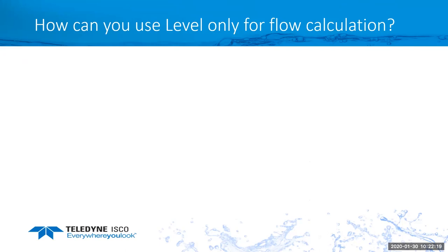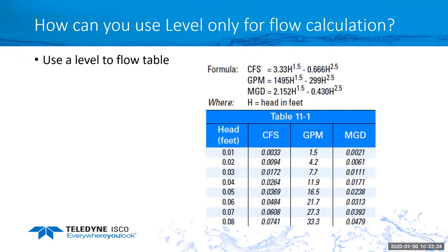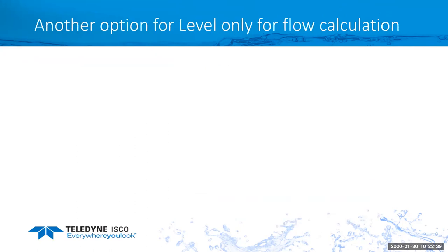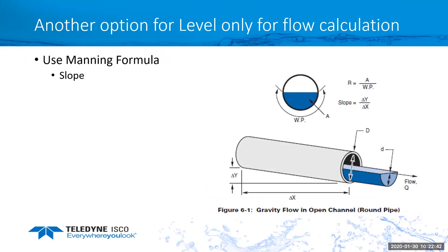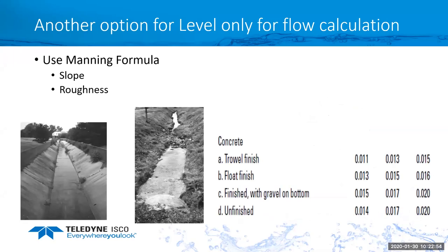So continuing on that, how can you use the level only to calculate flow? One, you can just use a level to flow rate table. The ISCO Flow Data Handbook has lots of tables in there depending on what your application is. Or you can use a flow calculation to determine your flow rate. Other options are using the Manning formula. If you have a round pipe, elliptical, or rectangular channel, you need to know the slope of the pipe, which is part of the velocity calculation, and you need to know the roughness. With the slope and the roughness, you can then use the level to calculate your flow.